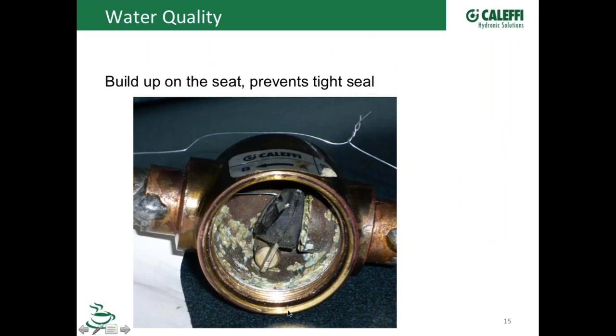I guess another good thing to mention on this slide, since you're still here, Bob, is two things actually. We do offer repair kits for our zone valves as well, where they include a new paddle for whatever reason. Those are a peroxide cured EPDM paddle, and they're going to be very resistant to a lot of torturous elements or applications. But if for whatever reason you do need to replace it, you can get a repair kit with that new paddle, along with a new C-clip, as well as a new O-ring for the bottom cap.